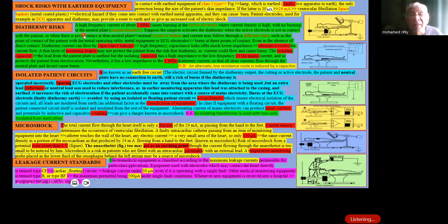Diathermy risk, as we know that diathermy works at a frequency of around 1 megahertz, which is a frequency not inducing ventricular fibrillation, but can induce burns, and this is the basis of coagulation. So we have an active electrode used by the surgeon and a neutral electrode, which is spread over a large area of the patient. So the current density is very low. This is why we don't get burns unless there is a fault, or the surgeon is using the electrode and there is no connection, or there is a fault in the neutral electrode not touching the patient completely.